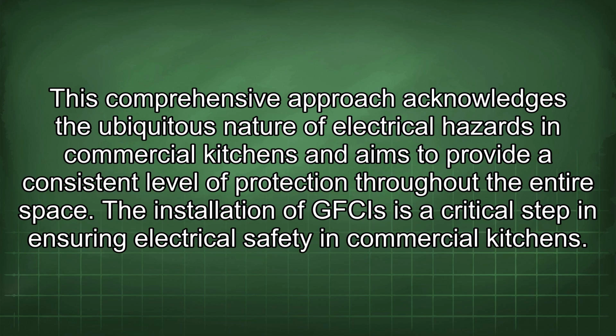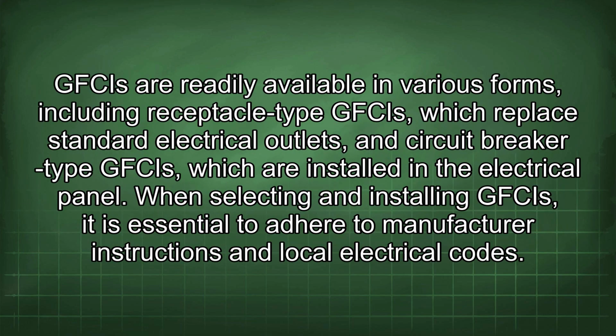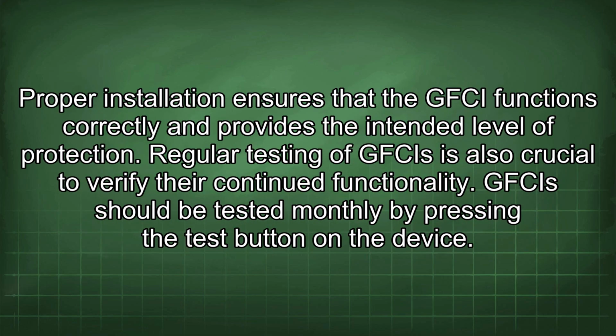The installation of GFCIs is a critical step in ensuring electrical safety in commercial kitchens. GFCIs are readily available in various forms, including receptacle-type GFCIs, which replace standard electrical outlets, and circuit breaker-type GFCIs, which are installed in the electrical panel. When selecting and installing GFCIs, it is essential to adhere to manufacturer instructions and local electrical codes. Proper installation ensures that the GFCI functions correctly and provides the intended level of protection.